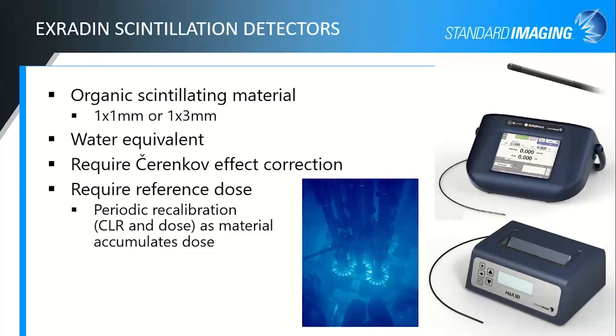The biggest benefit of the scintillators is that this organic scintillation material is water equivalent. One of the tricky parts on why these weren't widely adopted until just recently is that when you're doing scintillation measurements like this, you have to account for the Cherenkov light that's produced in the optical transfer fiber. It manifests essentially as a stem effect, an extra signal that is generated depending on the field size, depending on how much of this extra fiber is irradiated. And so we do have a routine to help you correct for that.